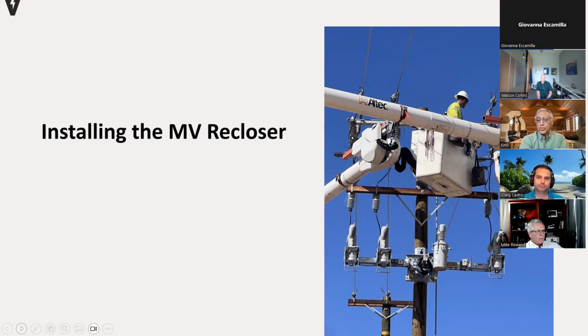As a result of this experience, we've migrated to requesting medium voltage interface for all our new sites. Wherever overhead lines are accessible and allowed by the AHJ, we prefer an overhead interface, since it reduces cost and execution time and avoids needing a ground-mounted switchgear.